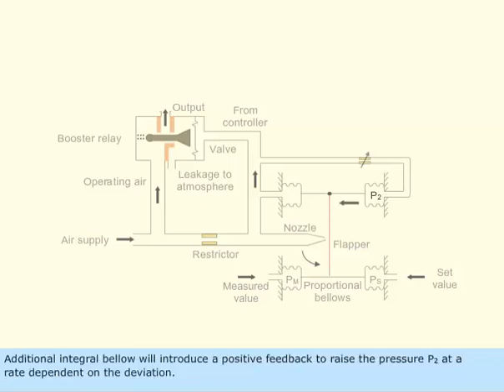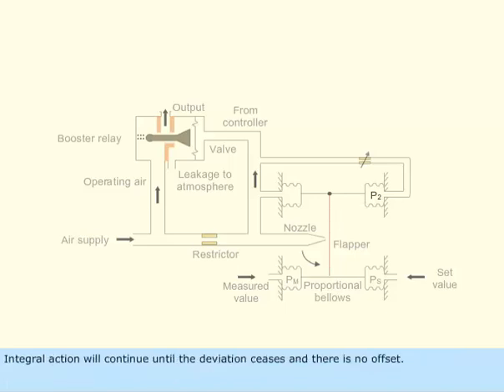Additional integral bellow will introduce a positive feedback to raise the pressure, P2, at a rate dependent on the deviation. Integral action will continue until the deviation ceases and there is no offset.